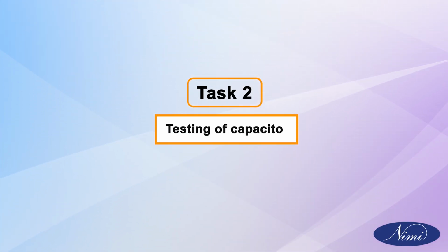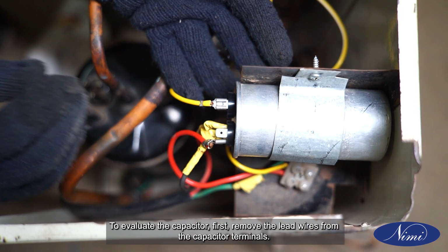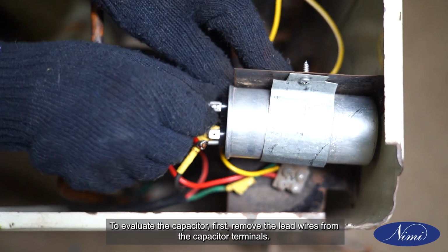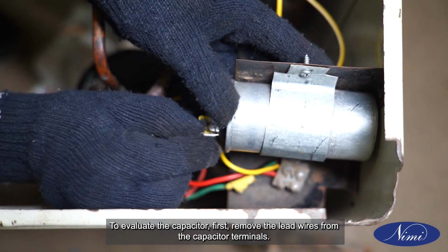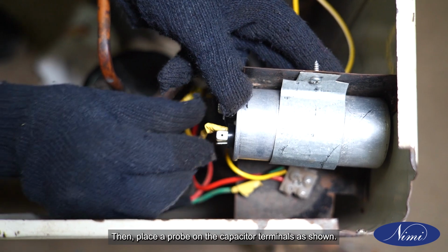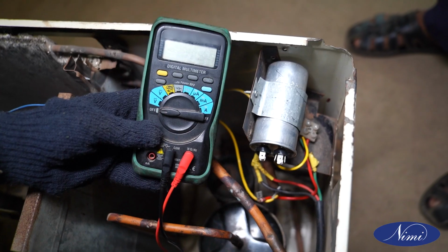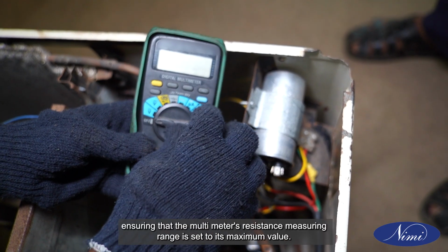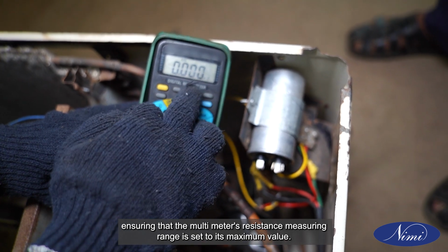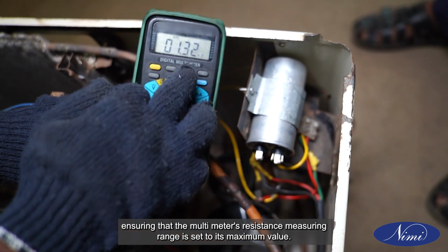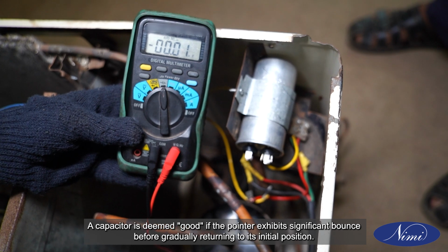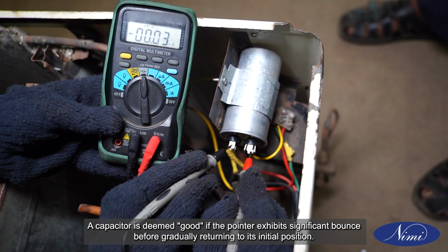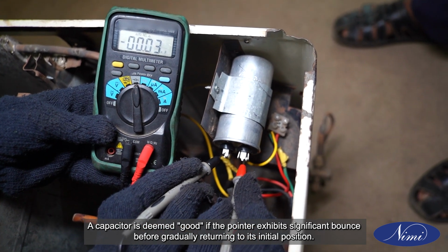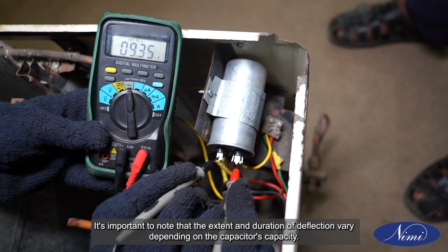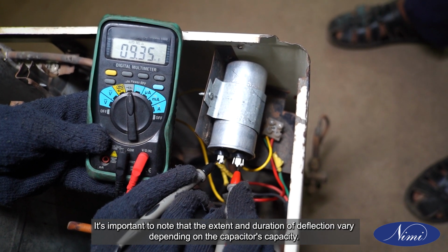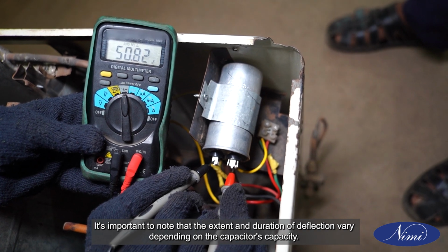Task 2. Testing of capacitor. To evaluate the capacitor, first, remove the lead wires from the capacitor terminals. Then, place a probe on the capacitor terminals as shown. Observe the pointer's deflection, ensuring that the multimeter's resistance measuring range is set to its maximum value. A capacitor is deemed good if the pointer exhibits significant bounce before gradually returning to its initial position. It's important to note that the extent and duration of deflection vary depending on the capacitor's capacity.